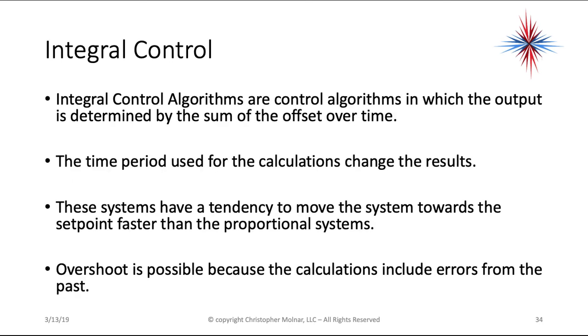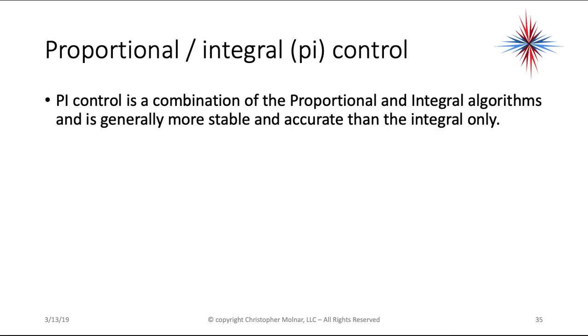Integral control algorithms determine output based on the sum of the offset over time. The time period used for calculations changes the results. These systems tend to move toward the set point faster than proportional systems, but overshoot is possible because calculations include errors from the past. PI control combines proportional and integral algorithms and is generally more stable and accurate than integral alone.